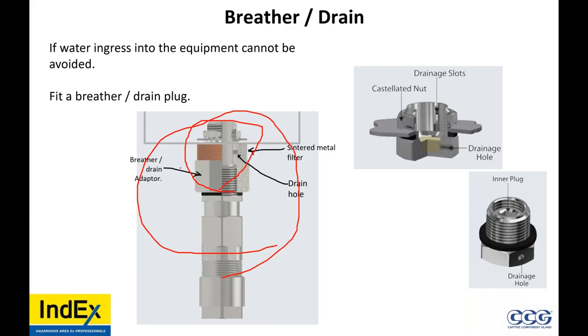Materials of construction. Yes, that matters. Brass is a problem. The use of a breather or drain: does this reduce the IP rating of the equipment? No, the breather drains have an IP rating. Obviously, if you're calling for IP67, 68, 69, ensure that the breather drain is rated for that. Read the certificate, read the IOMs.